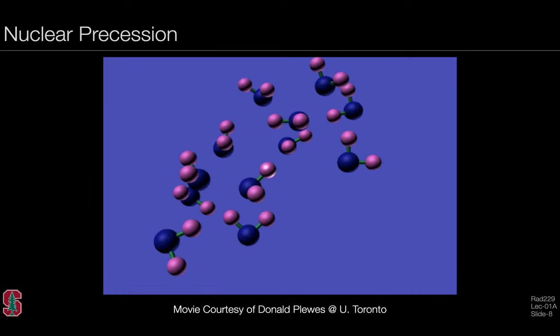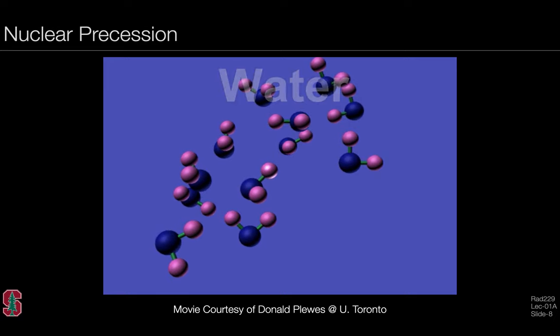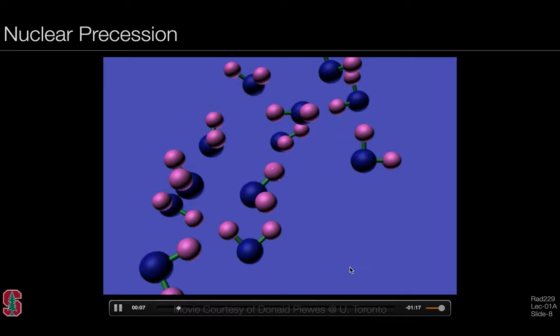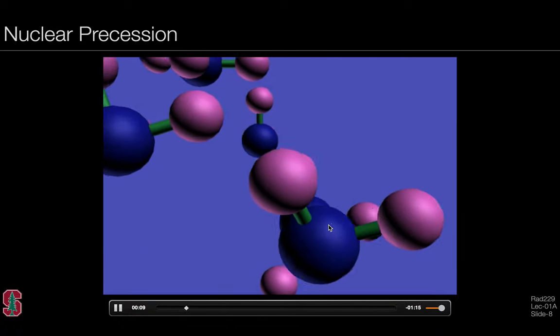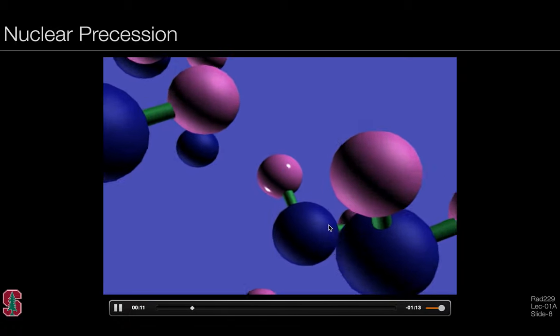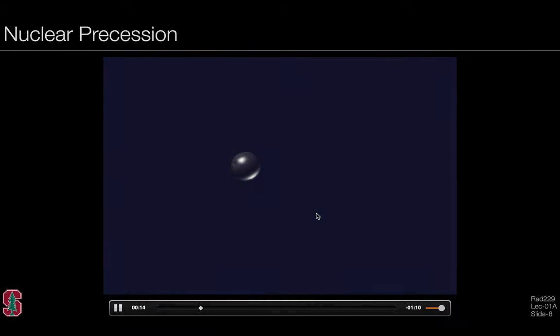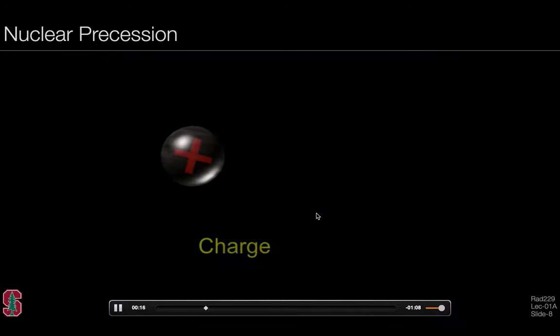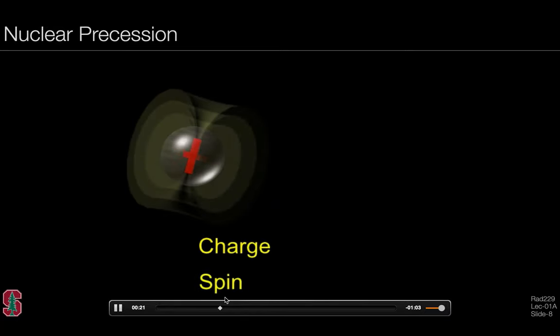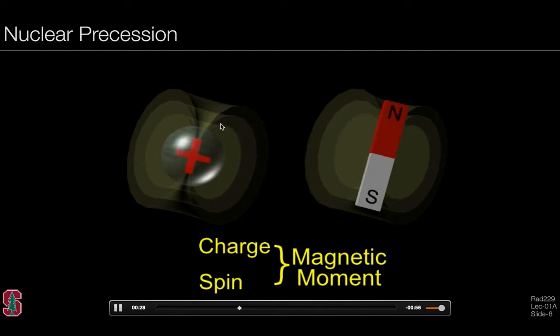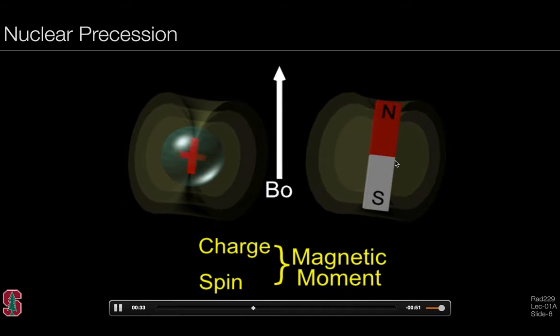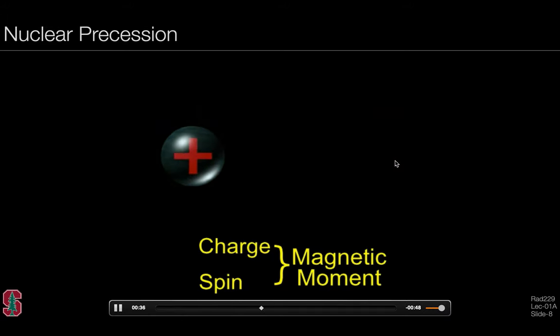When it comes to nuclear precession, we can zoom into a water molecule comprised of two hydrogens and an oxygen. Inside this hydrogen nucleus itself, it's positively charged. In combination with having charge, it has the inherent nuclear property of spin. That combination of charge and spin gives rise to a magnetic moment, meaning the hydrogen nucleus behaves like a tiny magnetic dipole. When placed into an external B0 field, it comes into alignment.